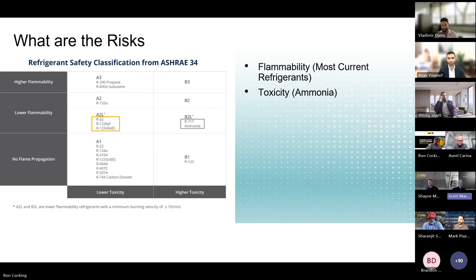Next slide. We look at risk mitigation. What we look for is self-contained systems. In these types of systems, the refrigerant is contained within the package, meaning none of it exits the boundary of the package or enters the space being cooled. We implement and design low charge systems that are situated external to the building, and then we add in the appropriate safety systems, which include leak detection, ventilation, alarming, and remote monitoring. These systems are always segregated from the facility, in that access is restricted to trained technicians and trained building personnel.